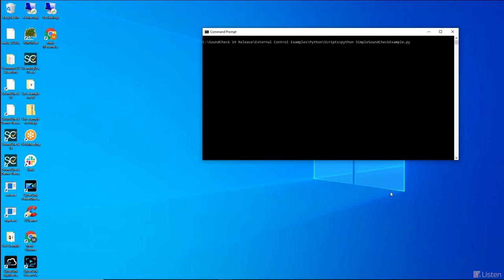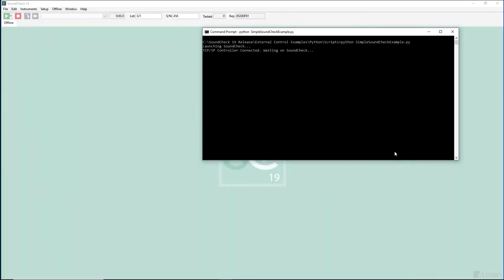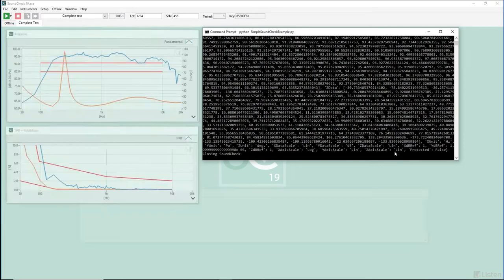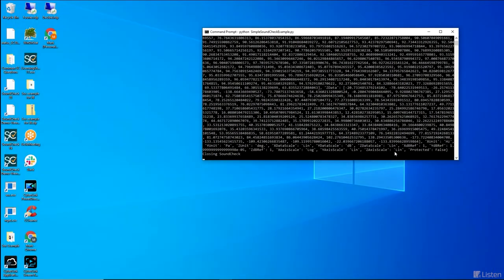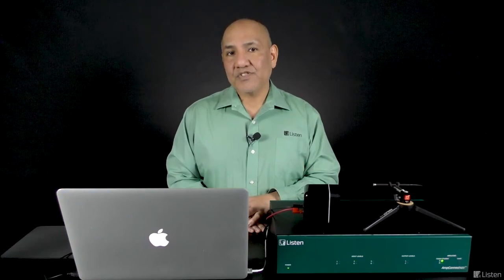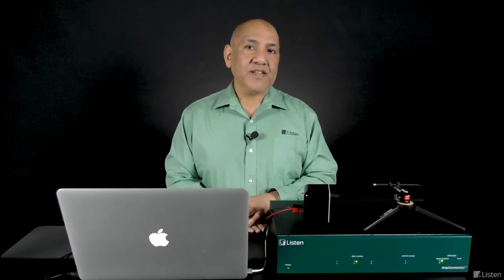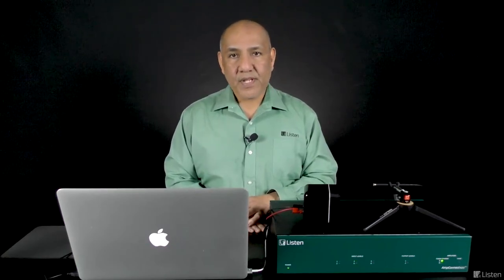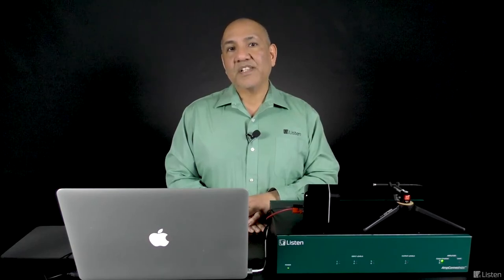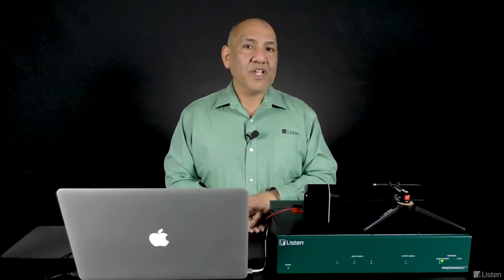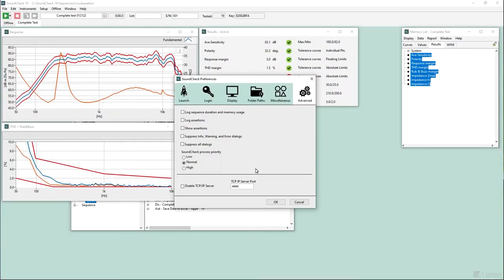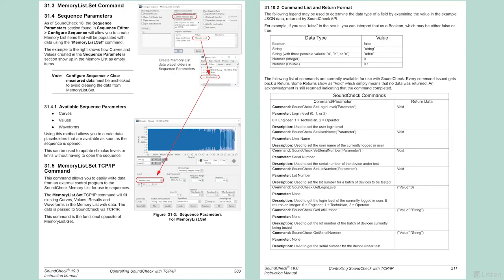Another powerful capability for production testing in SoundCheck is external control via TCP/IP. TCP/IP external control is operating system and programming language agnostic, so you can fully program in an environment that's familiar to you. The common application of external control on the production line might be using SoundCheck as one part of a larger overall test stand. SoundCheck handles all the audio tests for the device, but the full test stand may test other parts of your device like circuit boards, haptics, etc. SoundCheck runs in the background, and in some cases, the test operator may entirely run a different GUI and never even see SoundCheck. TCP/IP control is enabled through SoundCheck's preferences, and we provide external control examples along with full documentation, including the command set and return format to get you started.